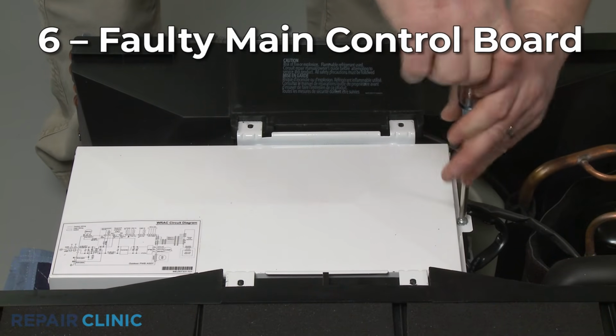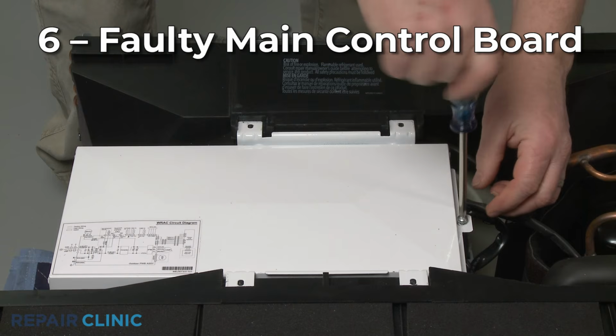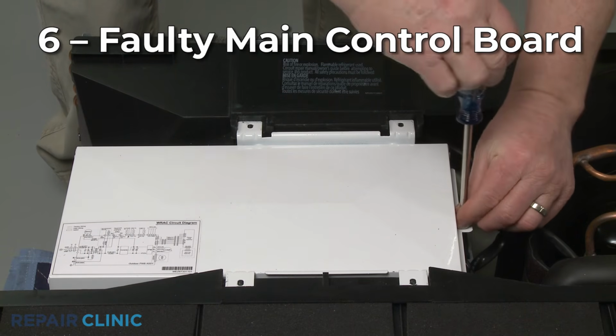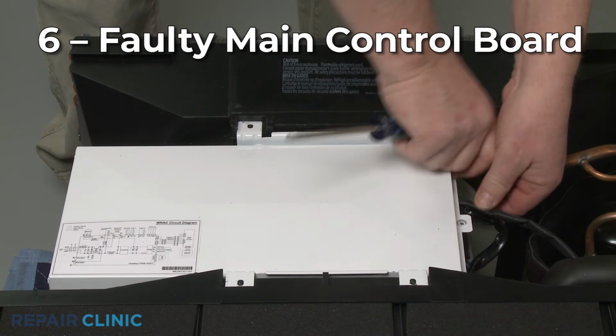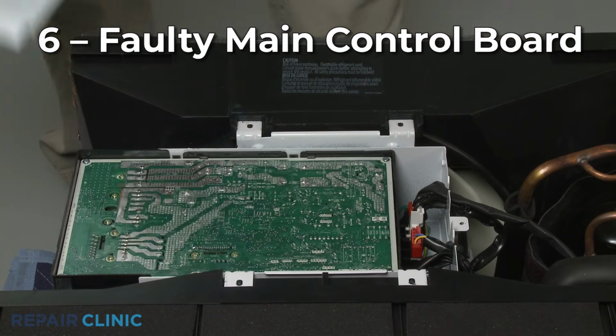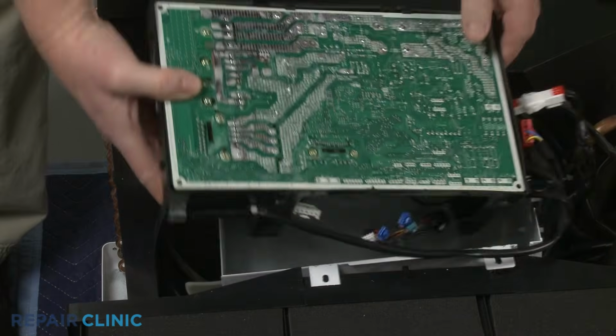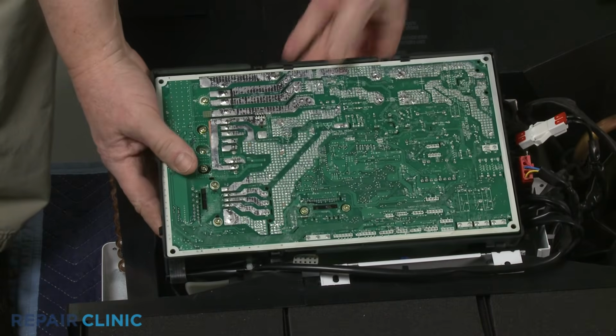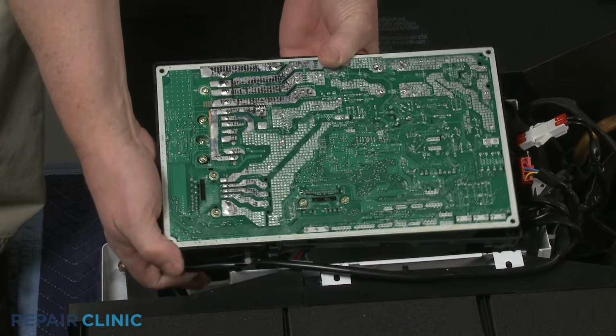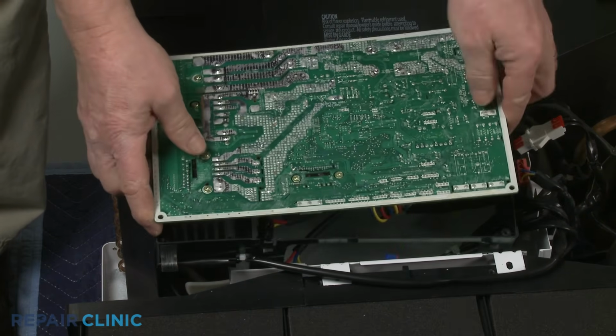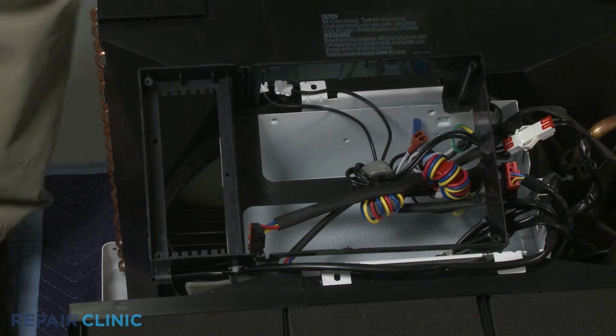The unit's main control board regulates the voltage to the compressor and fan motor, so a faulty board could result in the unit not cooling. Again, this is a less common problem, and you should verify the other more commonly defective parts are working properly before considering a control board replacement.